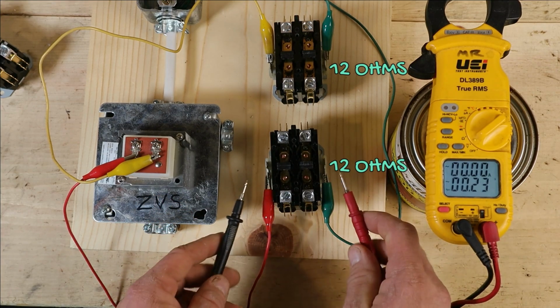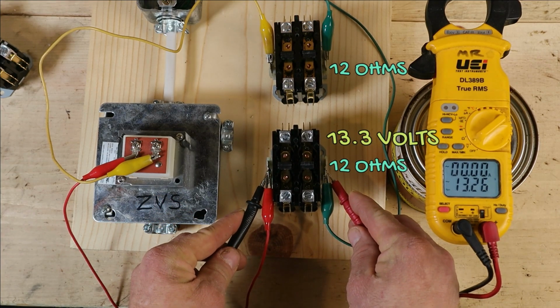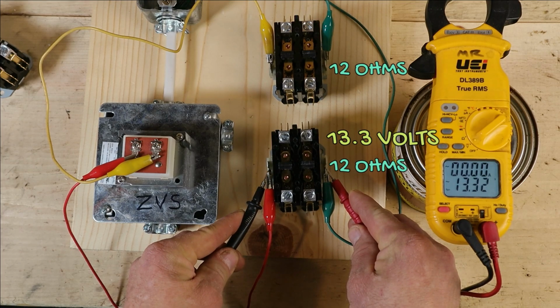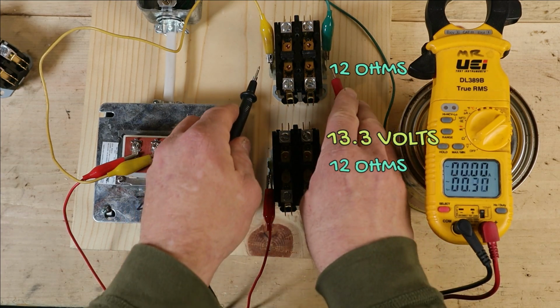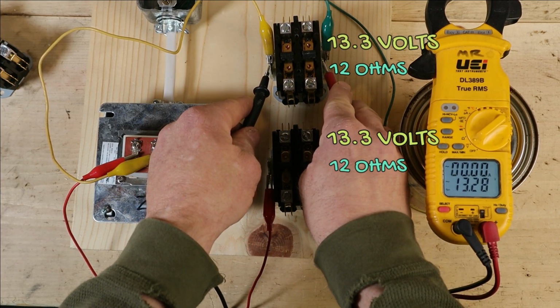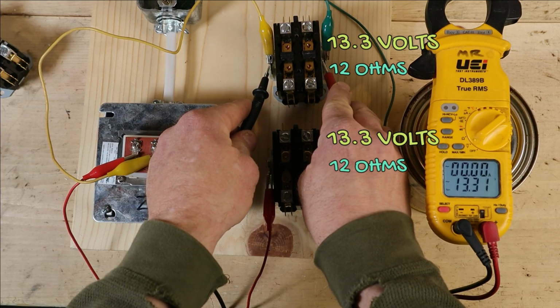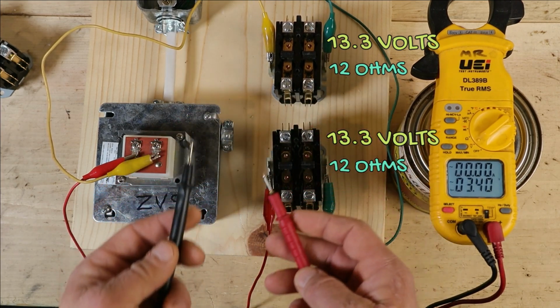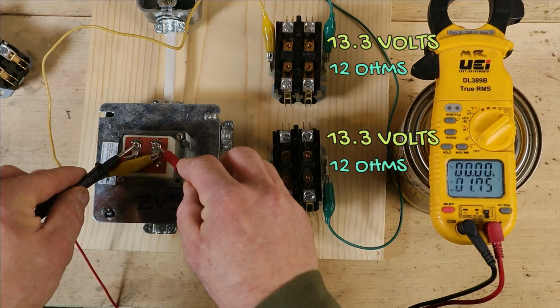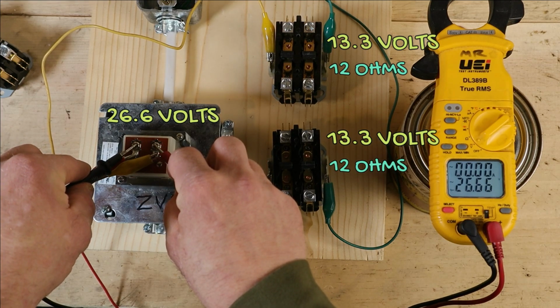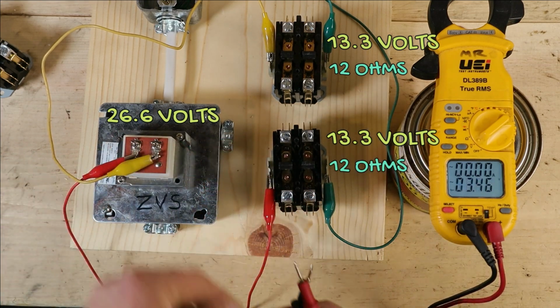So let's take a voltage reading across the first coil, and you can see we're reading just over 13 volts there. Now if we do the same thing on the other coil, you can see we're also reading just over 13 volts there. So we should be reading about 26.5 volts off the transformer, and there we go. So what's going on here?